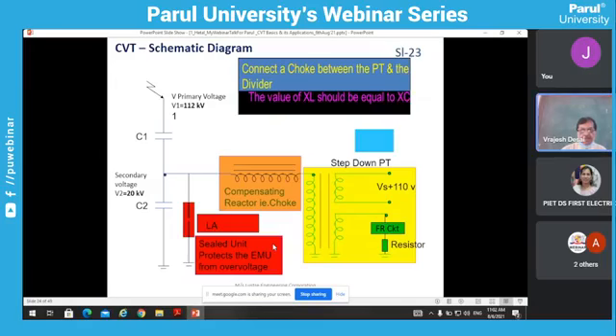So that is how the function of the reactor works, which is nothing but an inductive choke. Then, as I told you, in the schematic cross-sectional view I have shown the lightning arrester. The lightning arrester is provided particularly to protect the intermediate PT in case of lightning surge voltage and switching surge. In case of 400 kV, normally we have very predominant lightning voltage and switching surge. So this lightning arrester protects the PT primary side. On the secondary side, we have 2 to 3 windings, 110 volts, and then there is one FR circuit which is connected to damp out all the ferroresonance oscillations. We'll discuss in the last what ferroresonance is.